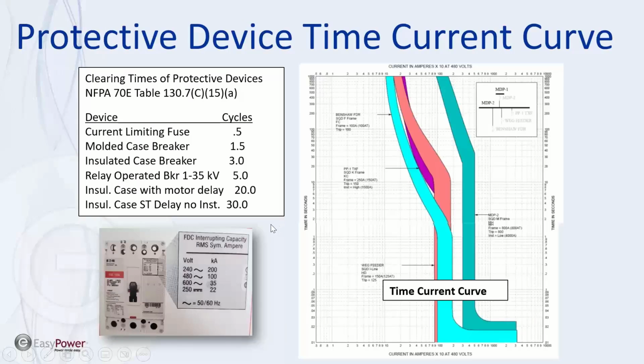So all breakers and all fuses, and I don't know if you can see me or not, but I have a breaker and fuses in my hand. I've got a small breaker that is a 20 amp breaker, and it's rated for 120 volts, and it also has a fault current of 10,000 amps. So this is a Home Depot style breaker. That's the highest rating that you're going to get at Home Depot, 10,000 amps. So you don't want to use that on a system that is higher than 10,000 amps.